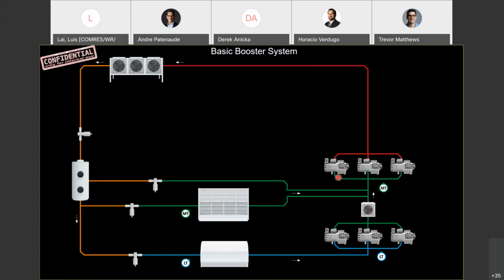Going into medium temp compressors, discharging up to a gas cooler. So right now they can manage with their iPro Rack 12 low temp compressors. They can handle up to 12 medium temp compressors. They can handle adiabatic gas cooling, where you've got adiabatic pads where you drizzle water over top and the condenser or the gas cooler feels like it's a wet bulb temperature, so the head pressures are lower. They can manage that today.